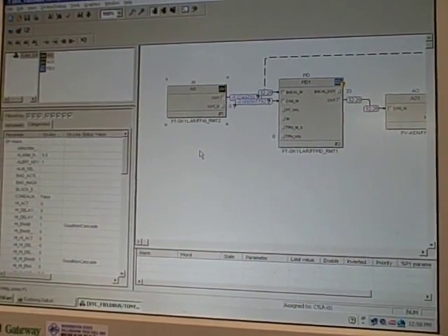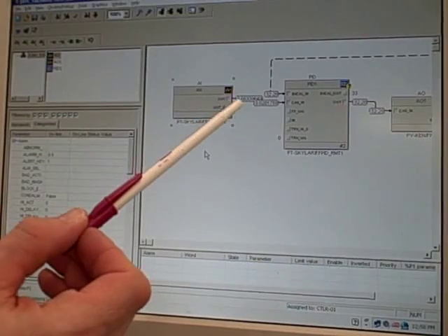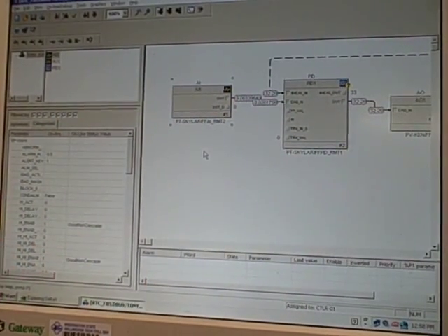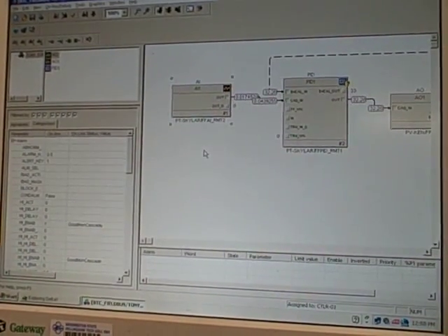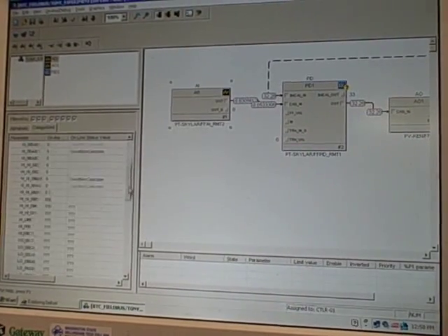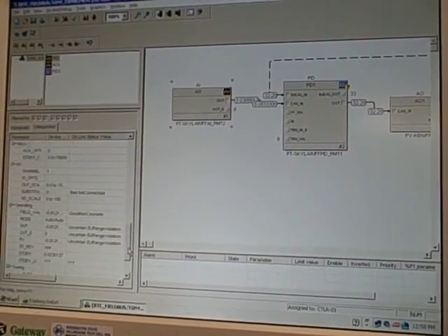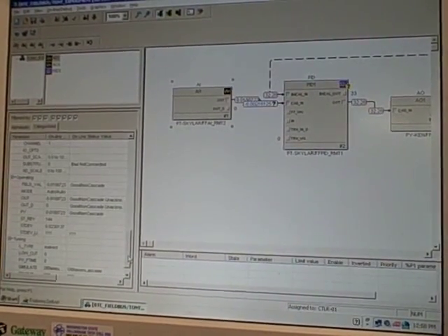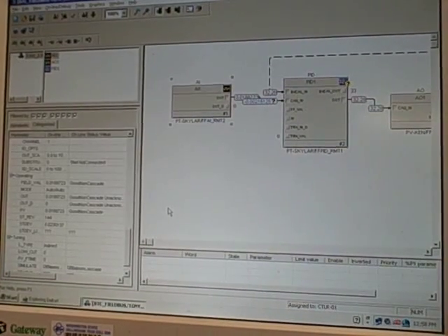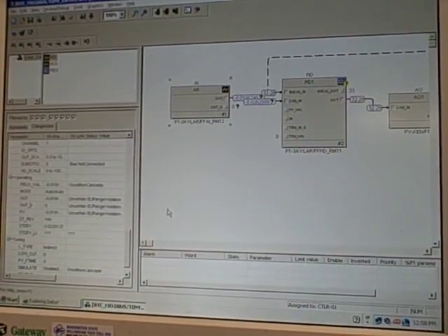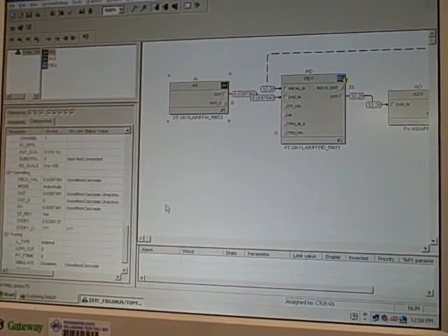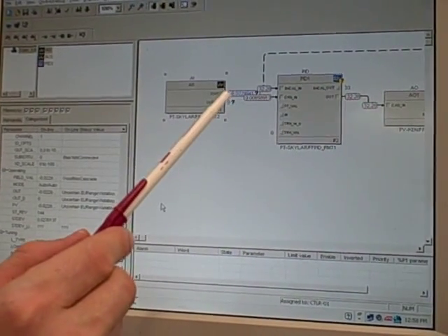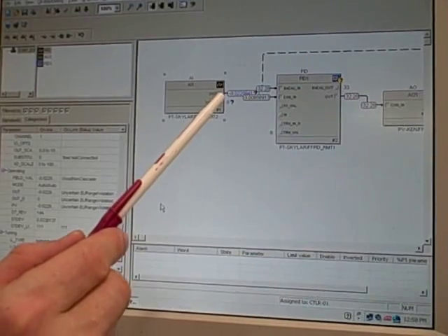What I want to show you right now is the live display of pressure that's being measured here, as well as status. One of the important concepts in Foundation Fieldbus is that every signal that is communicated between blocks has not only a value, a numerical value, but also a status that goes along with it. So I want you to pay close attention here to the number we see coming out of the analog block.